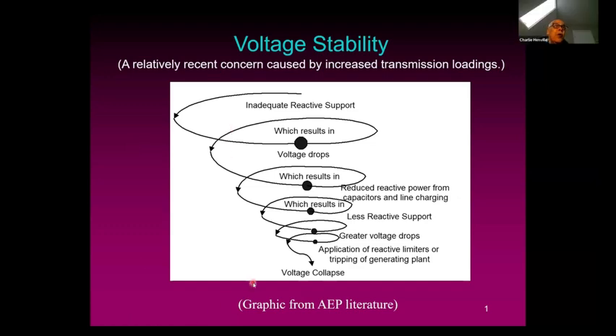Thank you, Koji. So today we're talking about the value or the importance of reactive power. And this slide shows what a friend of mine was trying to get the operators of a large power plant to operate their generators at the limits of their reactive power capability. And as some of you may know, it's very difficult to get operators to move close to the limits of equipment because they're worried that it might trip out unexpectedly. So he created this slide which shows how if you need the reactive power from a generator because of a voltage drop, then the voltage will go down, but the generator will try and increase the reactive power that it puts out, but it might not be enough.